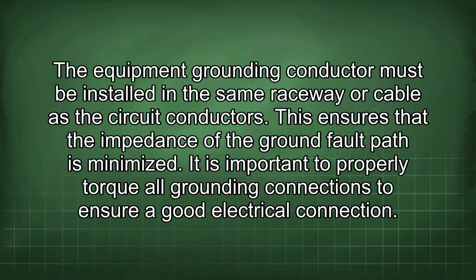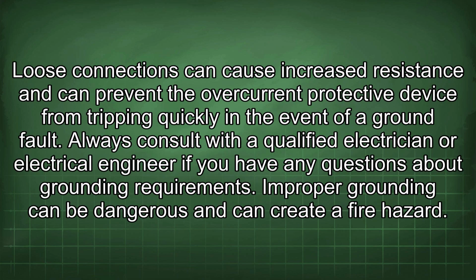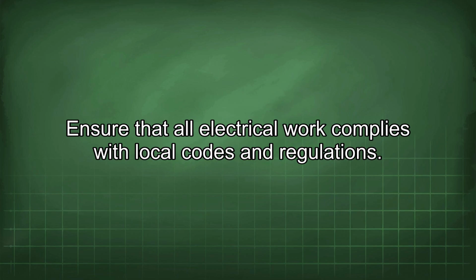The equipment grounding conductor must be installed in the same raceway or cable as the circuit conductors. This ensures that the impedance of the ground fault path is minimized. It is important to properly torque all grounding connections to ensure a good electrical connection. Loose connections can cause increased resistance and can prevent the overcurrent protective device from tripping quickly in the event of a ground fault. Always consult with a qualified electrician or electrical engineer if you have any questions about grounding requirements. Improper grounding can be dangerous and can create a fire hazard. Ensure that all electrical work complies with local codes and regulations.